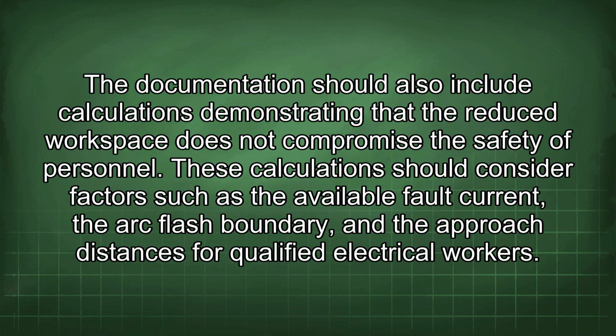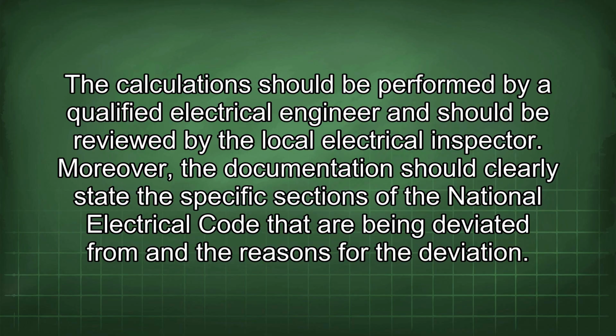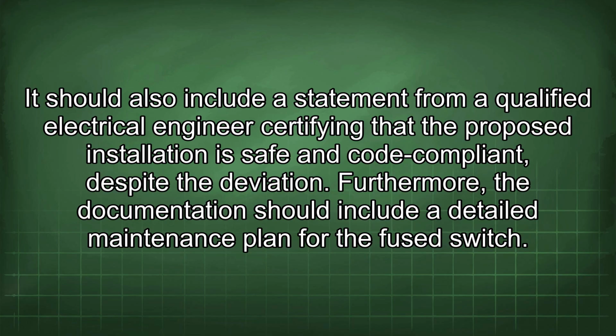The documentation should also include calculations demonstrating that the reduced workspace does not compromise the safety of personnel. These calculations should consider factors such as the available fault current, the arc flash boundary, and the approach distances for qualified electrical workers. The calculation should be performed by a qualified electrical engineer and should be reviewed by the local electrical inspector. Moreover, the documentation should clearly state the specific sections of the National Electrical Code that are being deviated from and the reasons for the deviation. It should also include a statement from a qualified electrical engineer certifying that the proposed installation is safe and code compliant despite the deviation.